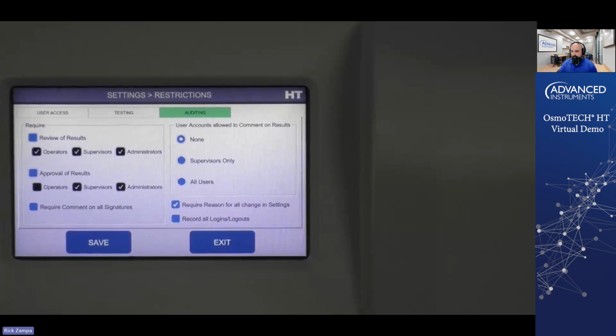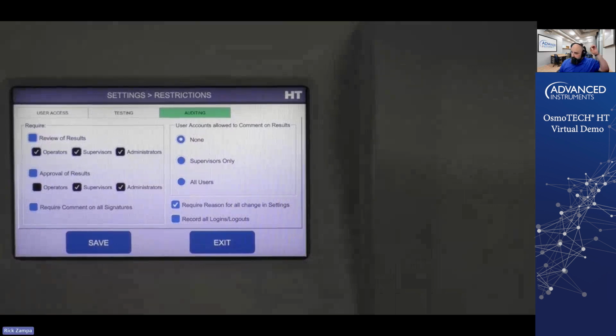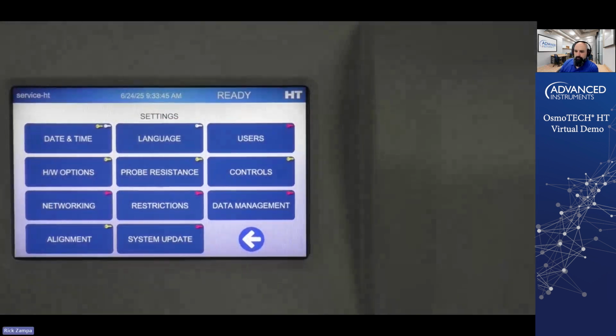Like I said, if you're in a GMP environment, in quality control or something like that, you'd want to turn this signature capability on, as well as all the user logins and sample ID information. If you're in a research or a formulation early development type situation, you don't have to turn on any of this, but you can still get all your information from the system. So you can review results and choose who is to review. You can require signatures on all comments, or require comment on all signatures, I should say. And then you can require reason for change in all settings. I've got that turned on, as I mentioned. You can also record every login and logout on the system if you would like to. Exit out of that. So those are the restrictions of setting up your testing.